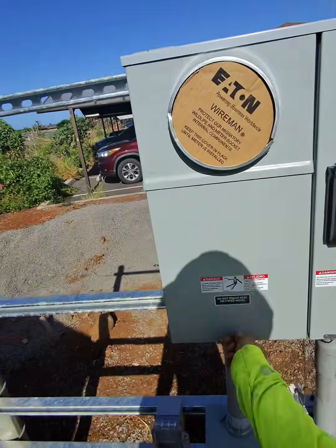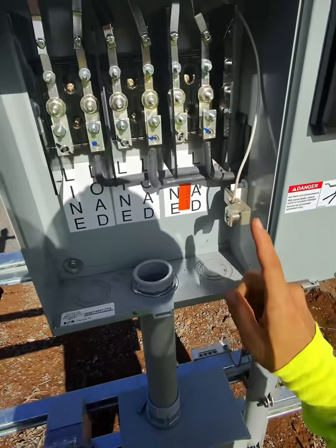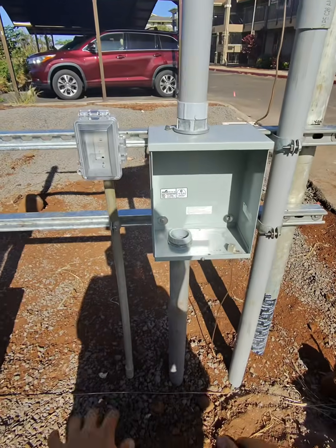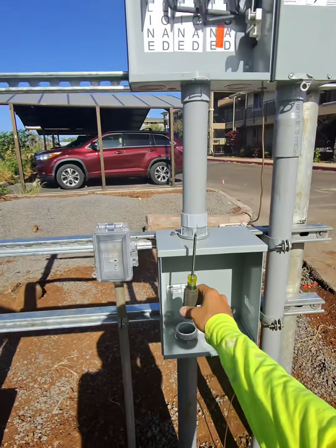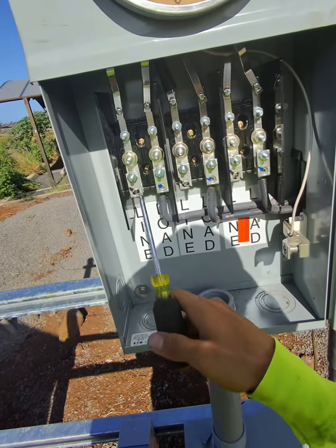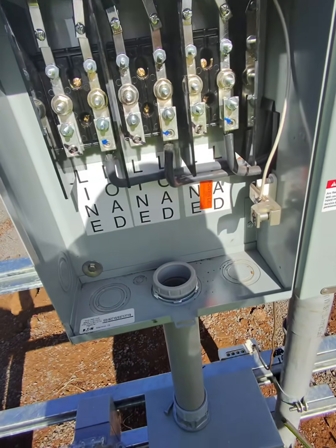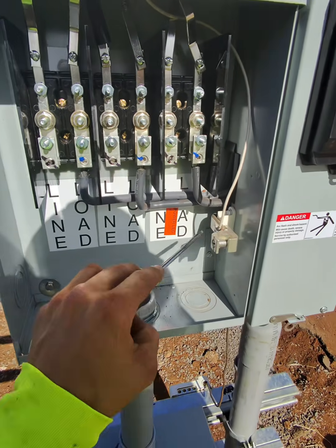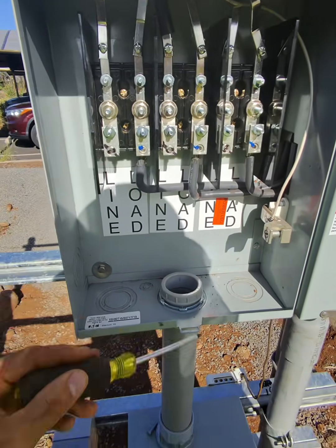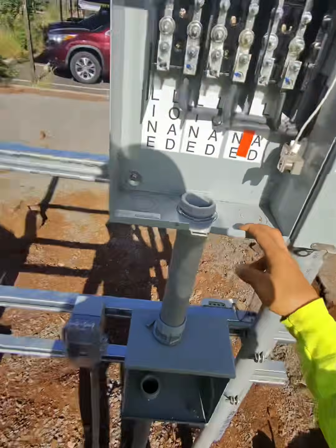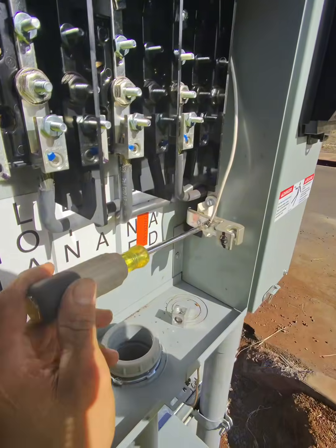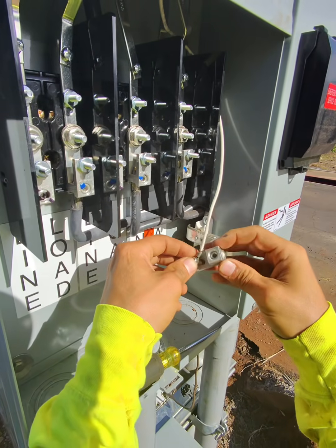This is our meter main breaker equipment. I need to get the supply side bonding jumper. I believe the utility company is going to bring their 3 conductors and a neutral up into here, land the neutral into here, land the conductors into here. This box still needs to be bonded to our bonding system. So I'm going to add a lug onto here and then bring a number 8 wire, sized by the size of the conductors, down into here just to hit this lug. So I'm just going to take this little jumper out. Okay, got my new screw. And this goes just like that.